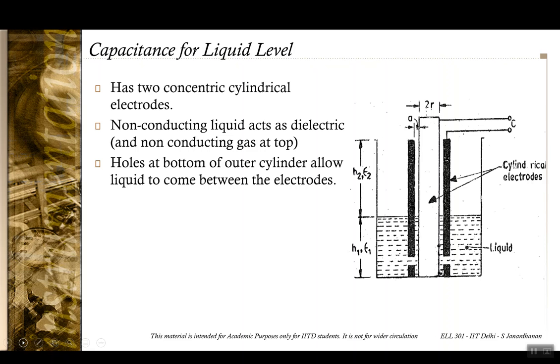This concept of having two different dielectric media and taking a parallel combination of the capacitance can also be used for liquid level measurement. Here, in the tank that is holding the liquid, you have two concentric cylindrical rods. The liquid whose level is to be measured should be non-conducting, and the gas in which it is kept should also be non-conducting. Since most gases are relatively non-conducting, that's not a very tight constraint, but what is important is that the liquid is non-conducting so that it can act as a dielectric.